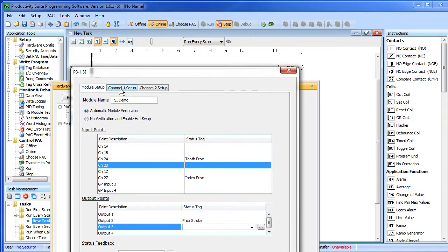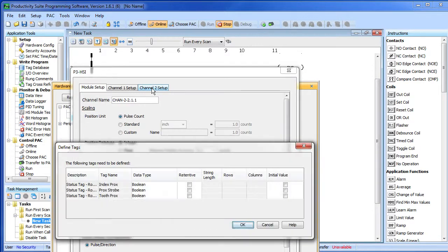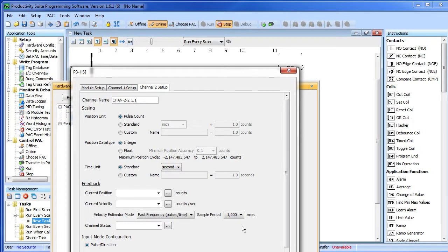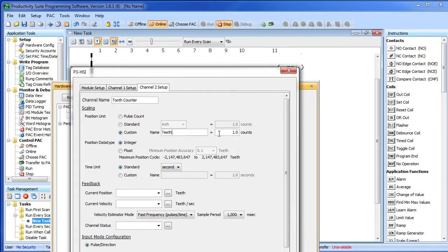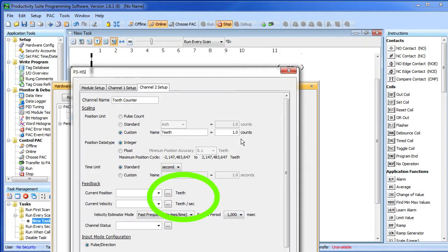We're not going to use channel 1 yet – the encoder is connected to that one – so let's go straight to channel 2. The software is telling me I defined some new tags and it's asking me if I want to create them. Sure – I really like that it does that for me. Let's name this channel tooth counter and since we want to count teeth, let's change our units to teeth. We'll get 1 pulse per tooth so we don't need to change that. The cool part is now all of our units going forward will be in teeth – I love that feature.